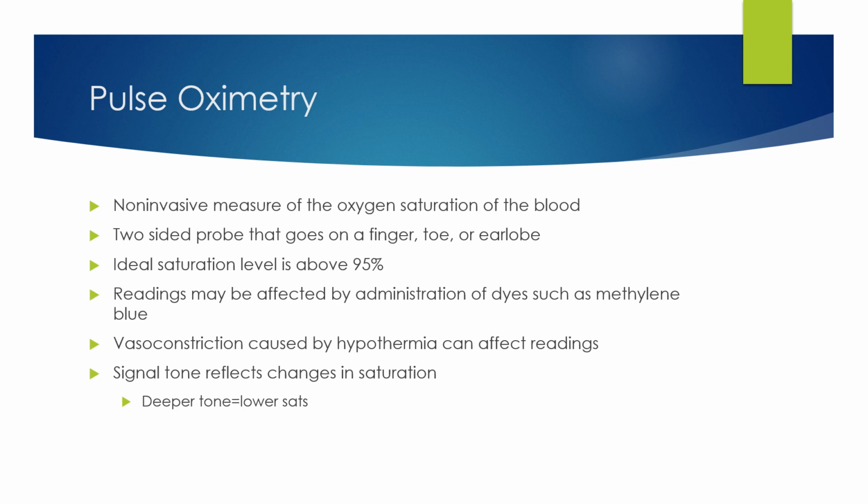And there is a signal tone to this as well that reflects the changes in saturation. So along with that heart rhythm tone, which is going to be a timed tone, you will also hear it get deeper for lower sats or higher for higher saturation. So you'll learn to differentiate and keep all of those in your mind.